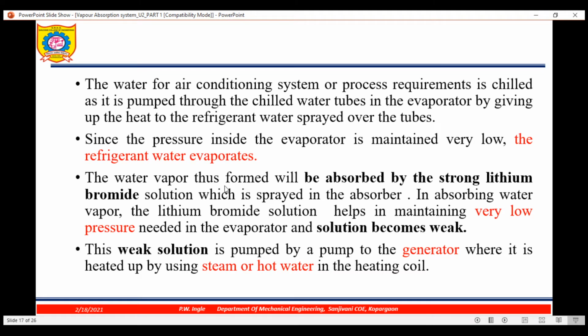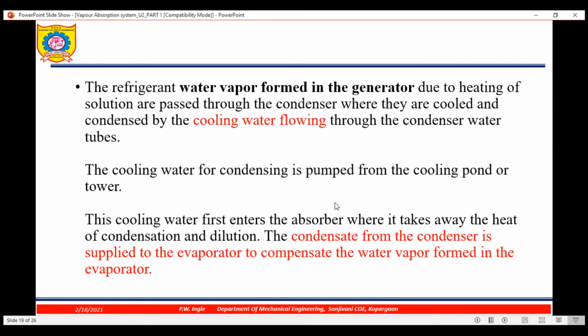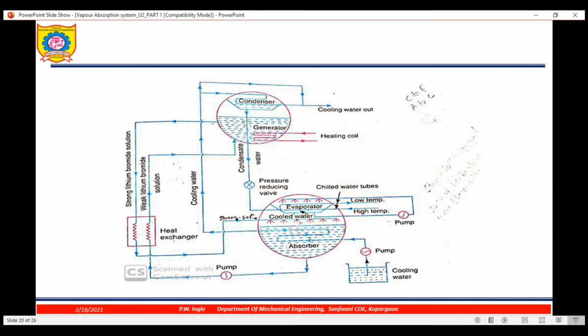Now the water vapor thus formed will be absorbed by the strong lithium bromide solution which is sprayed in the absorber. Here you see there is a LiBr solution. This LiBr solution will absorb the refrigerant. The refrigerant is also water. That water which was in vapor condition will be absorbed by the LiBr solution.